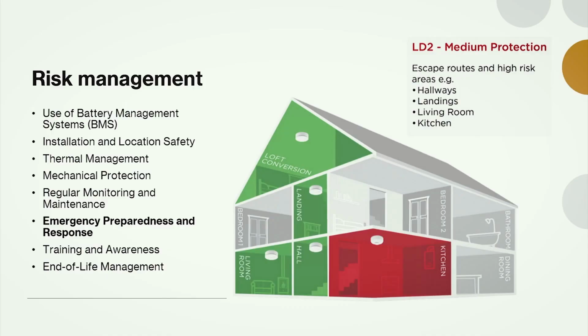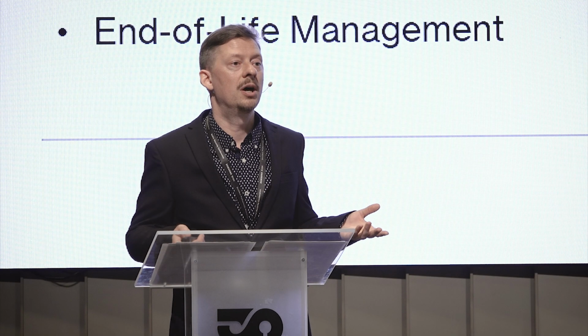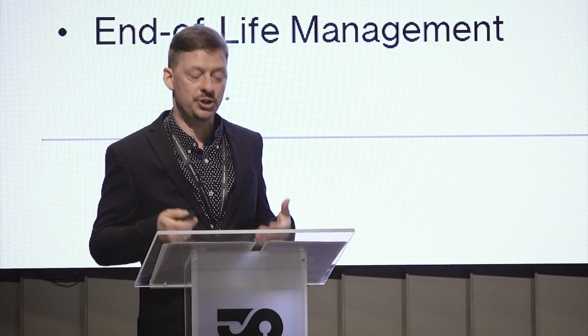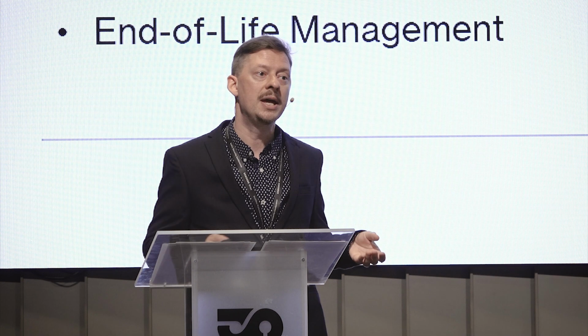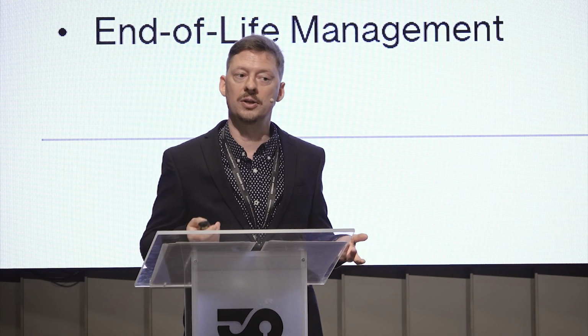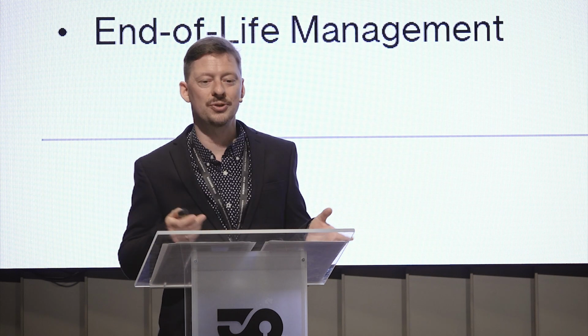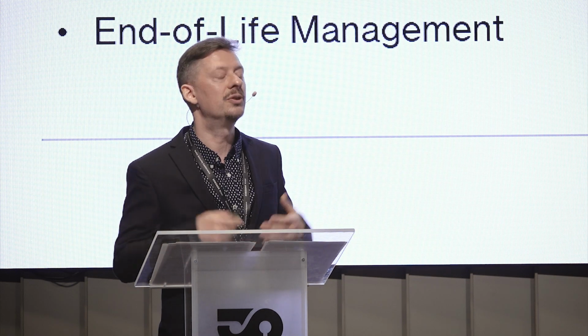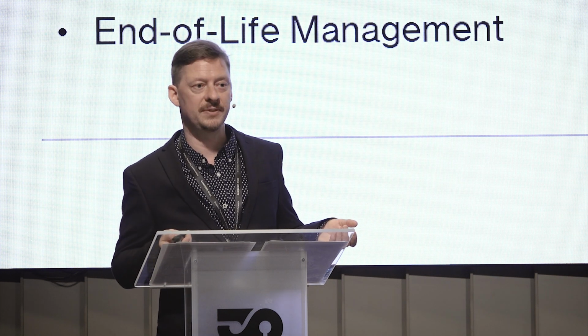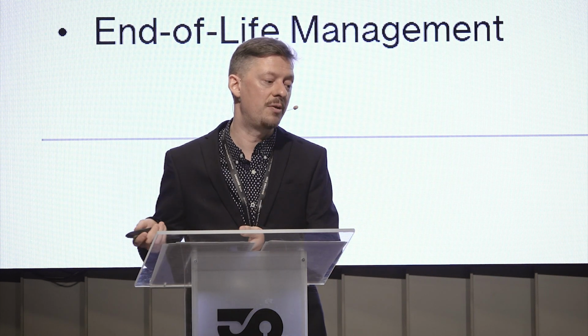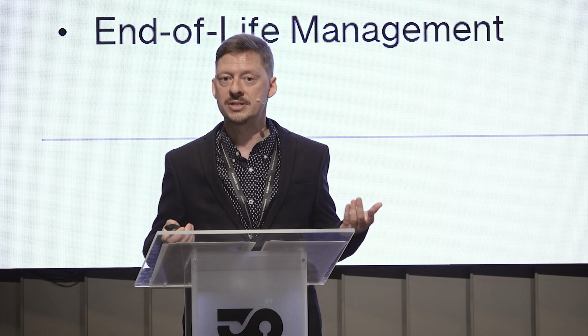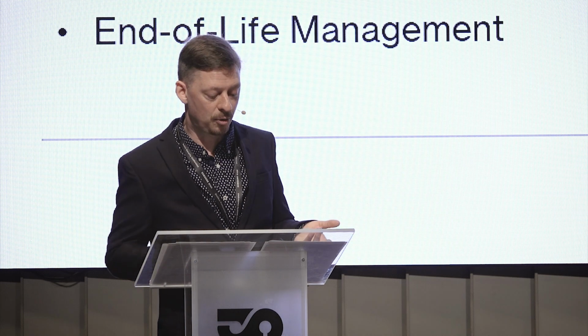And what do we do about emergency issues? It's recommended, in places where we install batteries, if it's not somewhere outside and far away from any risks, if it's somewhere in a house, we install fire detection systems integrated together with our systems. If faults happen, they happen very quickly, and you won't have time to look at them and think about what to do. You need an integrated system for fire safety, meaning if the battery is installed, for example, in a garage, we need a linked fire alarm system, so even if you are in the bedroom, you can hear that a problem has happened.